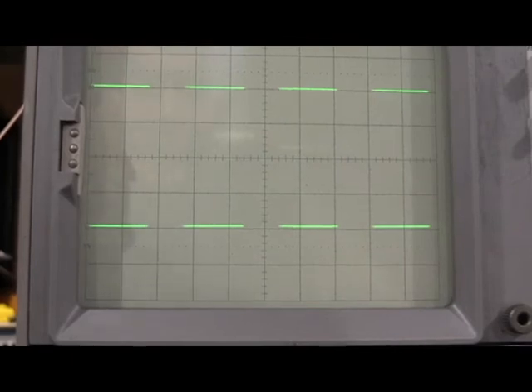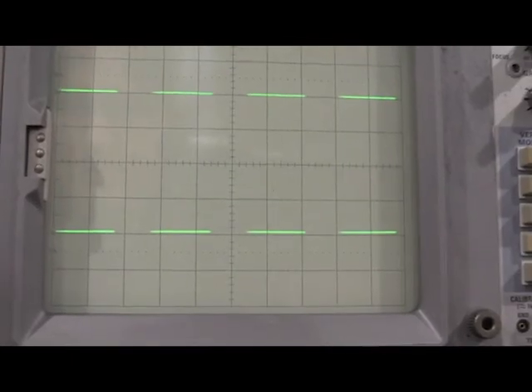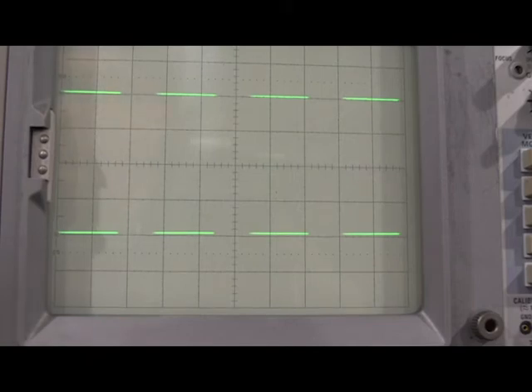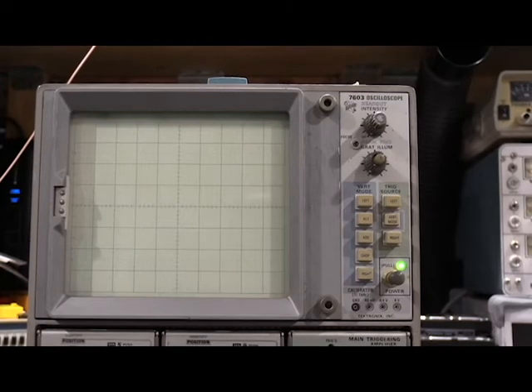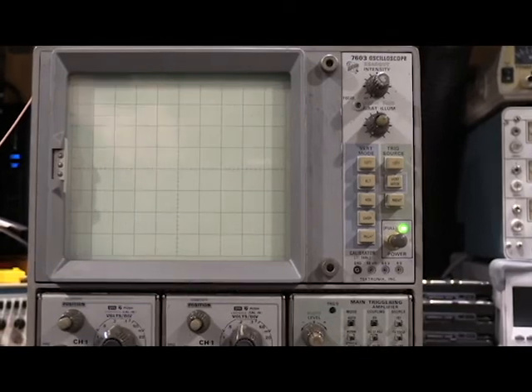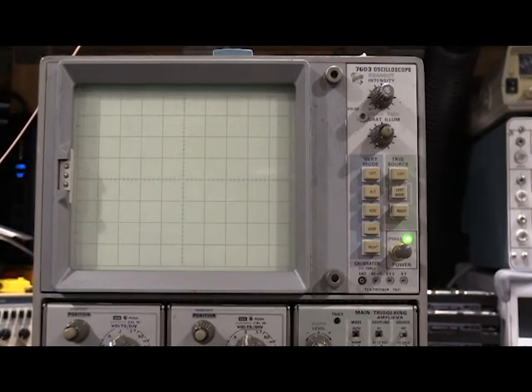Okay, checking the chop mode operation. This is the resulting waveform after hooking up the probe and getting it hooked up to the time base. For this one, you actually have to pull the power supply out of the back of the scope slightly because you need to hook up to test point 67, which is actually right smack dab in the middle of the frame behind the power supply. So it's working. Now I got to put the power supply back together again. Okay, so the chop functionality was the last piece of the vertical section. So that actually concludes the vertical section of the scope. Next up is going to be the triggering system, and we will take a look at that.